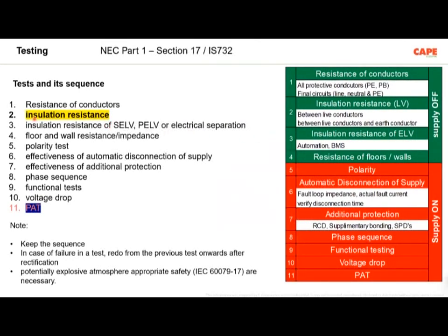One of them, test number 2, is insulation resistance. The minimum insulation resistance between a current carrying conductor and earth must be higher than 1 mega ohm. If the resistance is lesser than 1 mega ohm, you are supposed to rectify the problem immediately. Now, I have also included a test number 11.